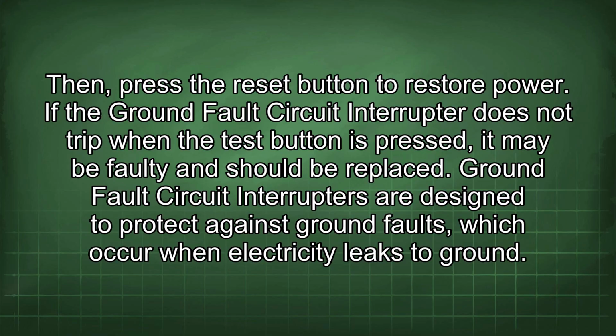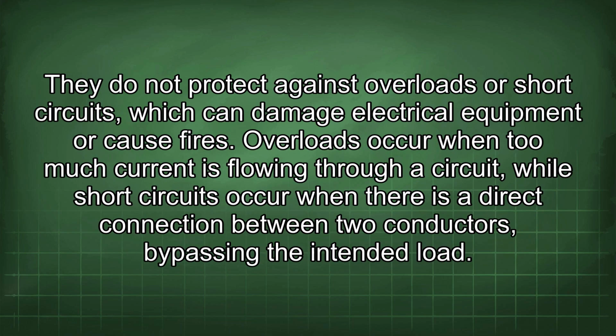Ground fault circuit interrupters are designed to protect against ground faults, which occur when electricity leaks to ground. They do not protect against overloads or short circuits, which can damage electrical equipment or cause fires. Overloads occur when too much current is flowing through a circuit, while short circuits occur when there is a direct connection between two conductors, bypassing the intended load.